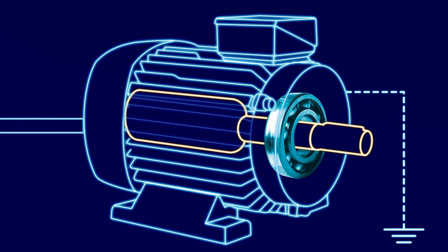In search for weak points of the insulation, it arrives at the motor bearing. As soon as it has found a weak spot, it breaks through all of the surfaces and the insulating lubricant in the bearing and leaves damage along the way, as we saw at the beginning. During operation, our little devil is not alone.